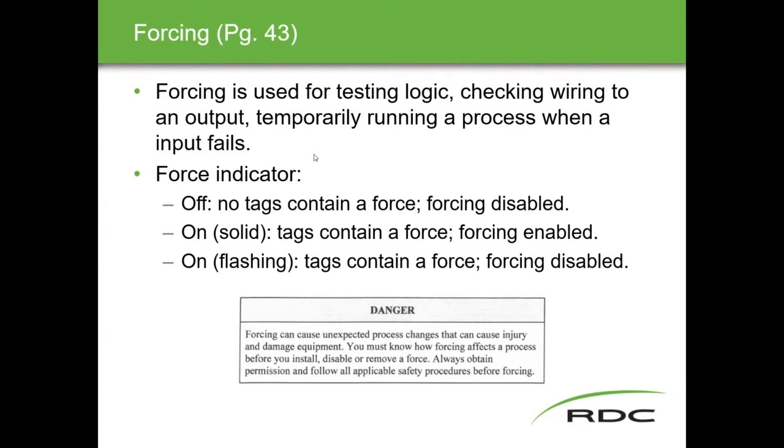It's important to know that, because if you open up a program and you see something that's forced, that should trigger you to go, okay, that can't be good, because forcing is usually only done when something in the field has failed or you're testing something. You normally wouldn't have any inputs or outputs forced in a normal running situation.